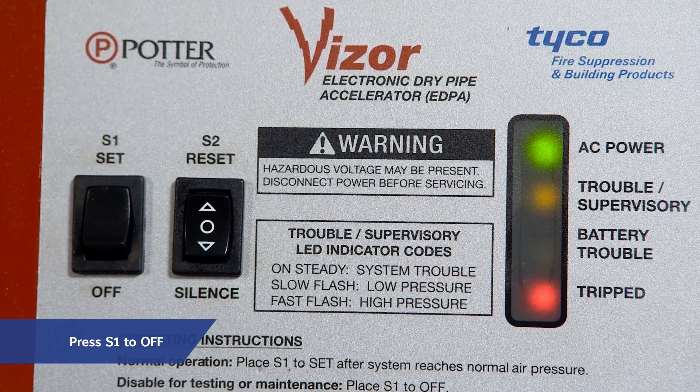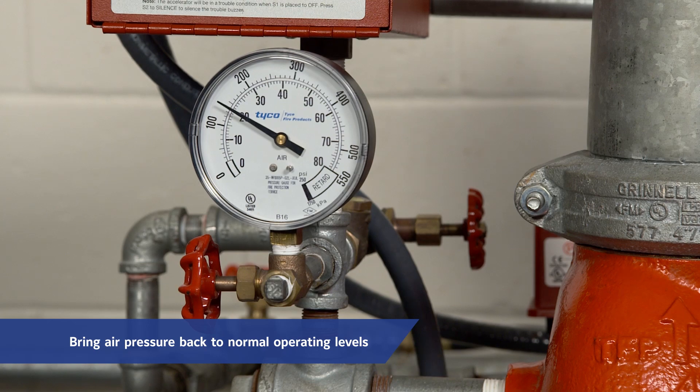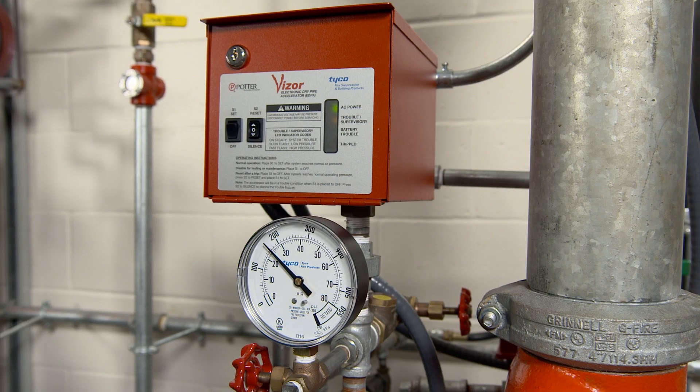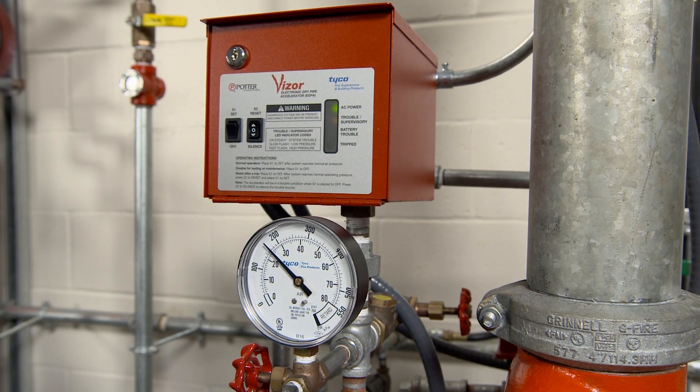For a tripped system, place S1 to off. Bring air pressure back to normal operating levels. Hit reset on S2, then place S1 to set. Note that the accelerator will be in a trouble condition when S1 is placed to off. Press S2 to silence to silence the trouble buzzer.